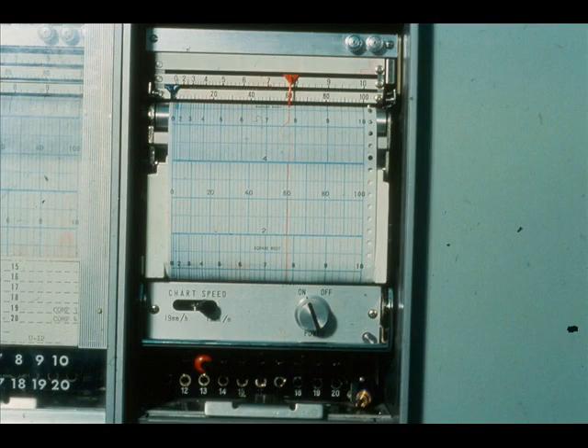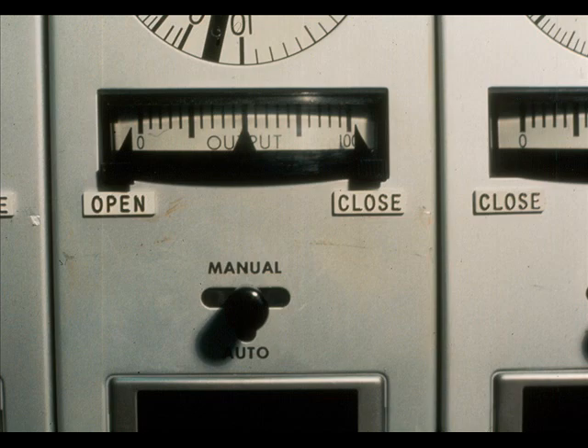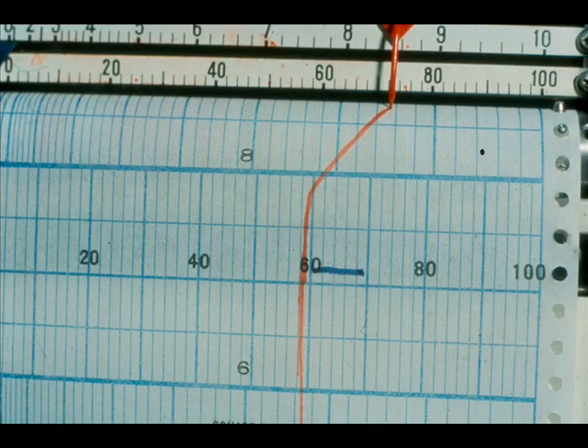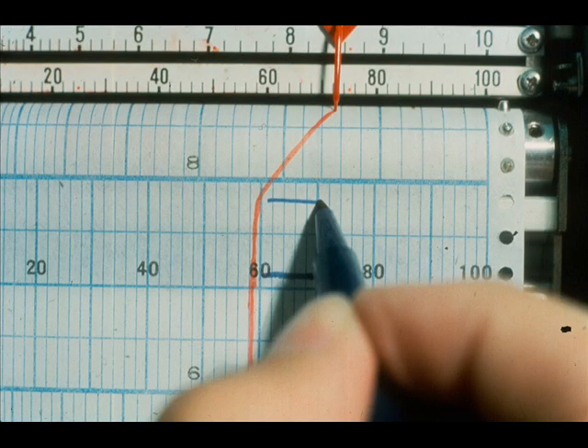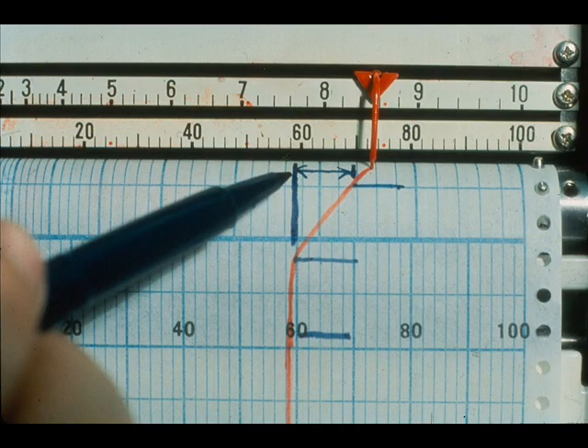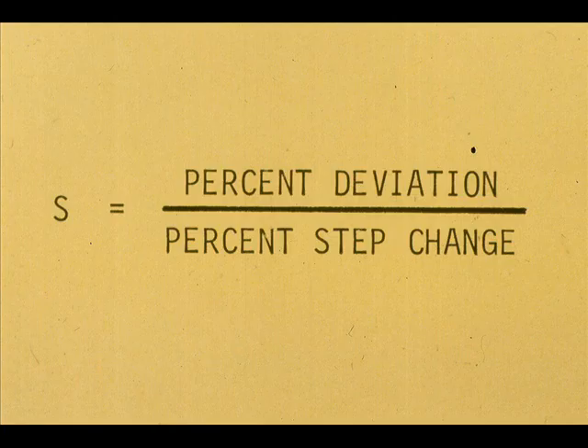Now let's repeat the procedure using live instruments. Line out the process on manual and make the percent step change. Simultaneously start the stopwatch and mark the chart. Measure the time to the open-loop response or the breakpoint of the curve, and mark the chart at the breakpoint. Let the chart run a second time increment equal to the first and mark the chart again. Transfer the slope of the curve up to the scale or read the percent of deviation off the chart, then divide the percent deviation by the percent step change to get the slope S.